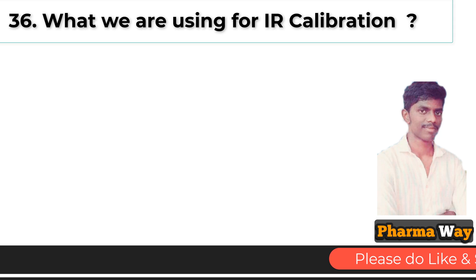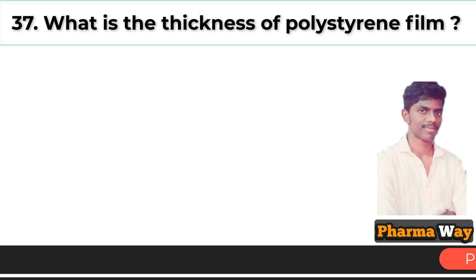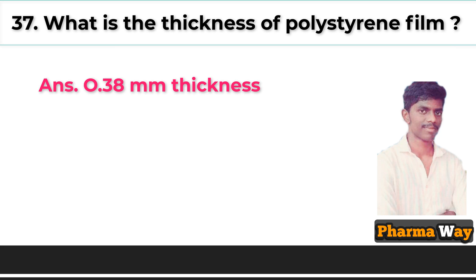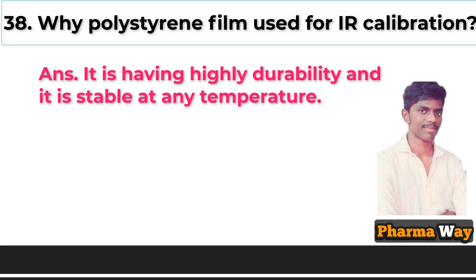What is used for IR calibration? Answer: Polystyrene film is used for IR calibration. What is the thickness of polystyrene film? Answer: 0.38 mm. Why is polystyrene film used? It has high durability and is stable at any temperature.